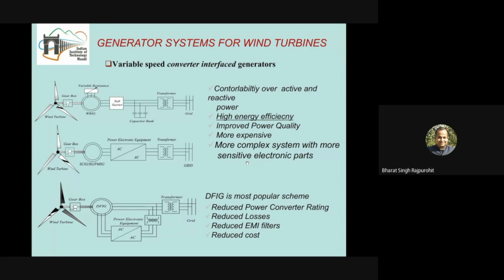Okay. Now, just see the first schematic, the topmost one on the left-hand side. This is known as a wound rotor induction generator, where the rotor has a variable resistance. This rotor is different from a squirrel cage induction machine rotor. In this case, the rotor has a winding, and this winding is terminated with a resistance, and this resistance can be varied. This scheme can be utilized to vary the speed of a wound rotor induction generator. By this, the system can be made variable speed.